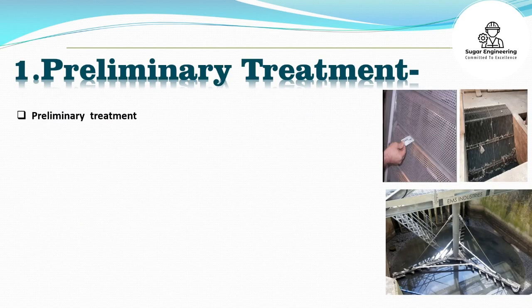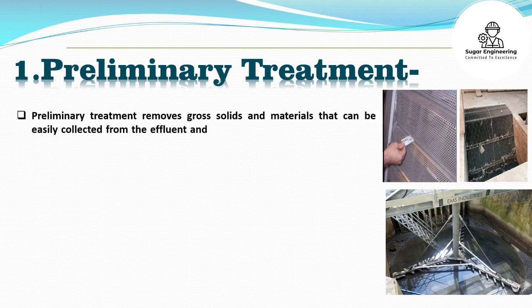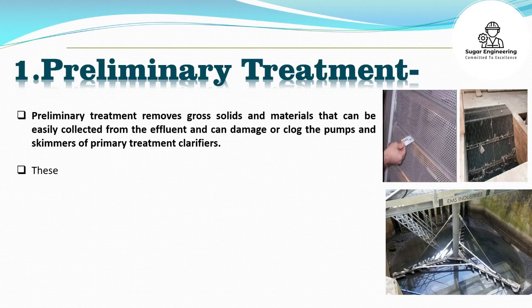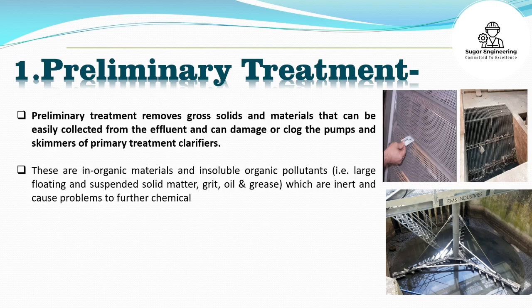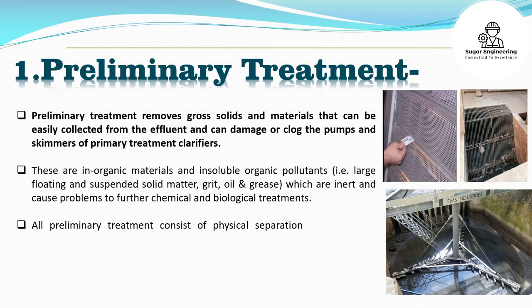Preliminary treatment removes gross solids and materials that can be easily collected from the effluent and can damage or clog the pumps and skimmers of primary treatment clarifiers. These are inorganic materials and insoluble organic pollutants — large floating and suspended solid matter, grit, oil and grease — which are inert and cause problems to further chemical and biological treatments. All preliminary treatment consists of physical separation techniques by controlling flow rate of effluent.